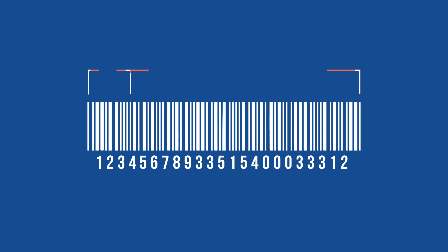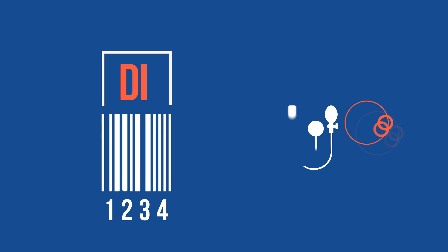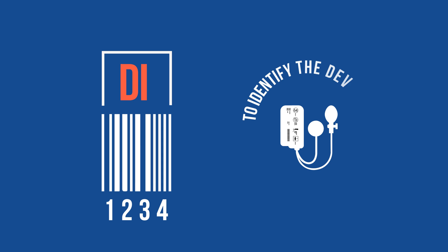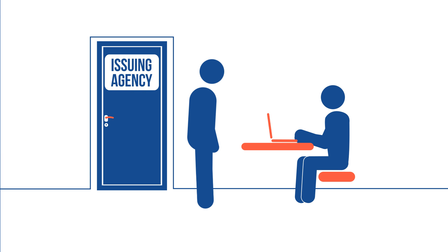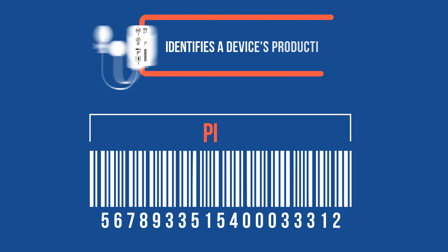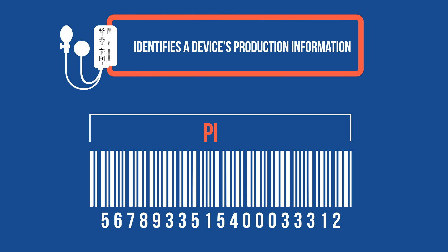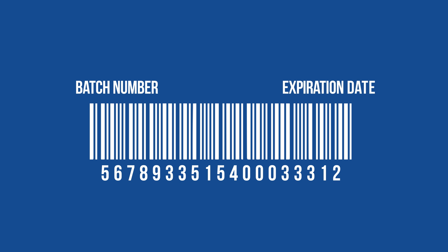A UDI consists of two parts: a device identifier and a production identifier. The DI portion of a UDI is used to identify the device type, and device identifiers are provided by an FDA-accredited issuing agency. The PI portion of a UDI identifies a device's production information, such as its batch number or its expiration date.